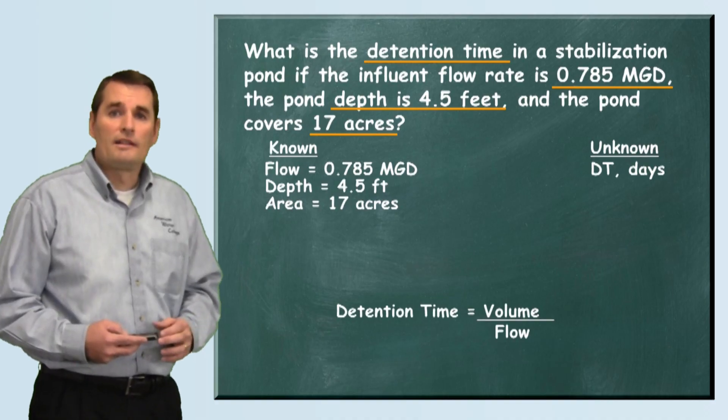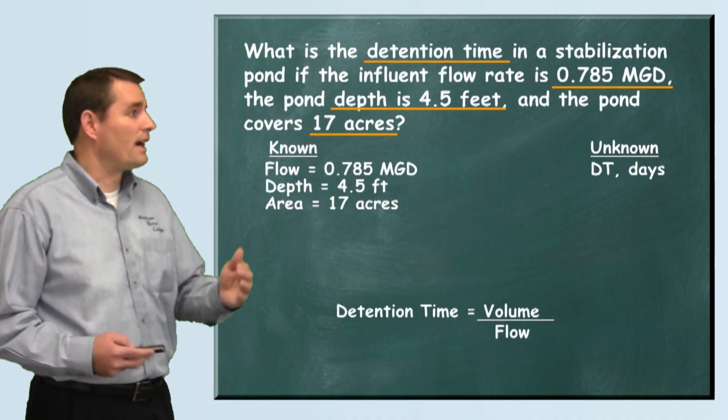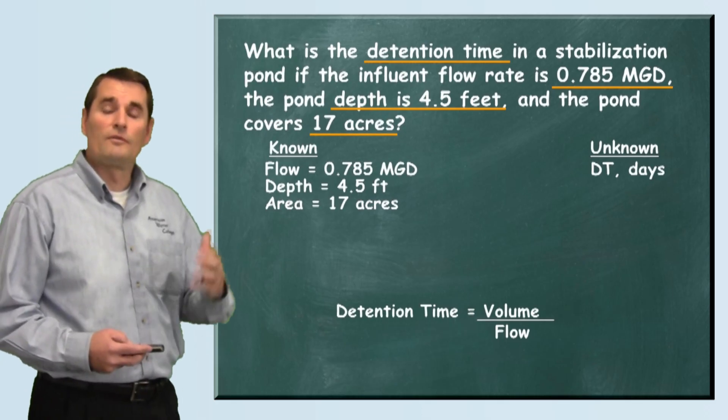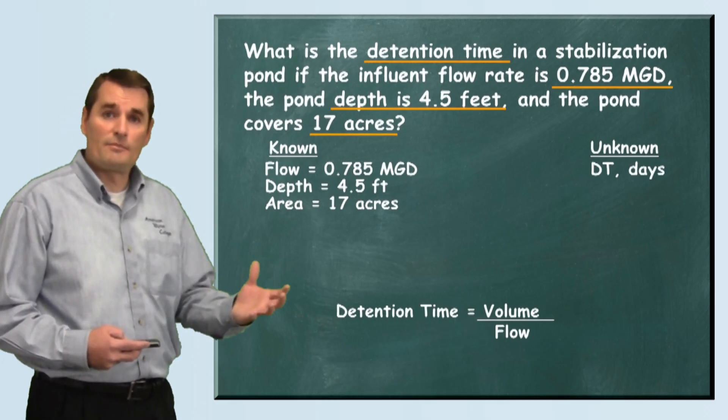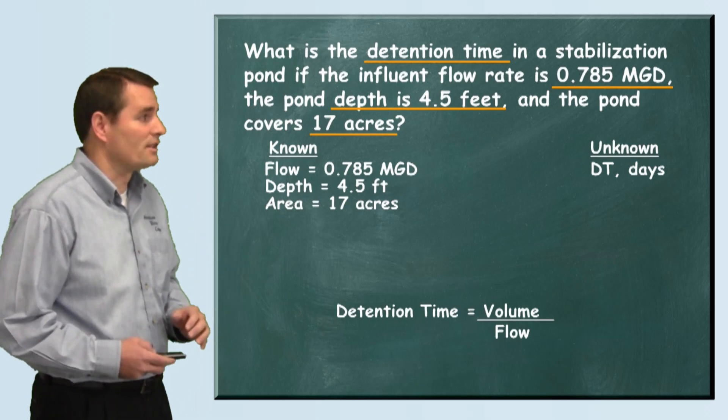Our detention time formula is basically detention time equals the volume divided by the flow. So if we can calculate the volume of this pond and divide that by the flow rate going into the pond, we'll have our detention time.